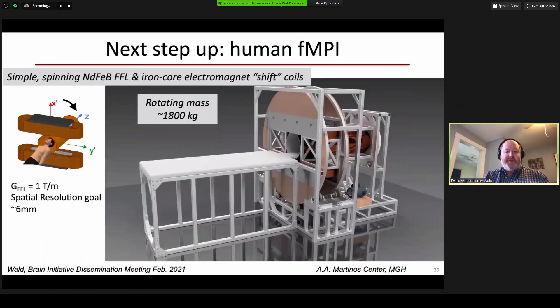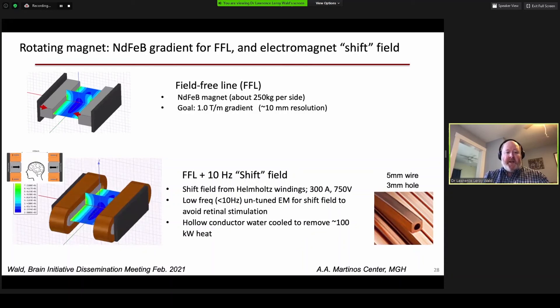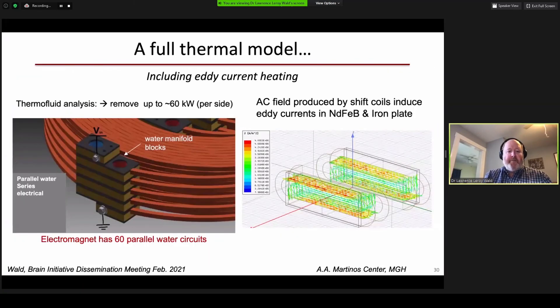Let me move on to the human scanner. Here's the same architecture basically scaled up: the gray rare earth permanent magnets create the field-free line, and the copper-colored components are the shift coils. We designed these neodymium iron boron magnets to give about one Tesla per meter gradient. They weigh about 650 kilograms and are currently being fabricated in China — about half done, expected in a month or two. The shift fields are driven by copper electromagnets generating about 50 kilowatts per side, cooled using hollow wire with very stringent water cooling.